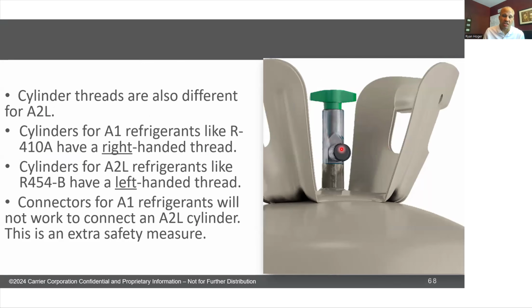The next thing that's changing is the threads on the top of the cylinder for these 20-pound cylinders. By the way, R-454B and R-32 are coming in 20-pound cylinders, so smaller than what you're used to with 410A, right? I'm assuming it's like potato chips, like just keep putting less and less in the baggie. I don't know what the deal is there. But it's 20-pound cylinders. It's probably related to some kind of transportation limit. But they're left-hand threaded for those 20-pound cylinders, meaning instead of righty-tighty, it's lefty-tighty.